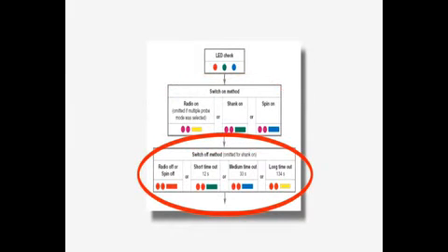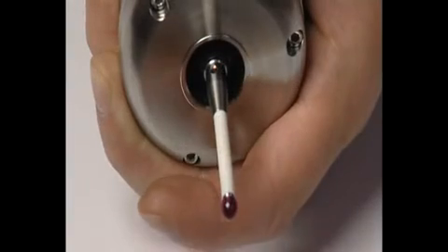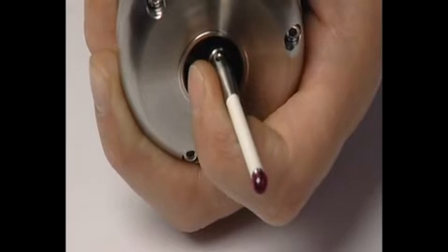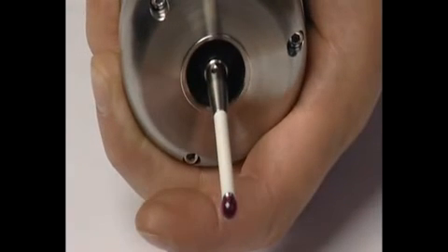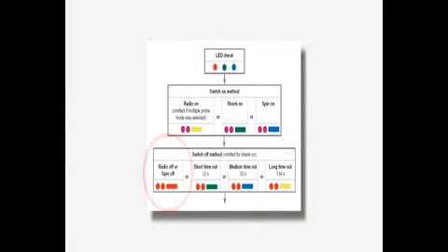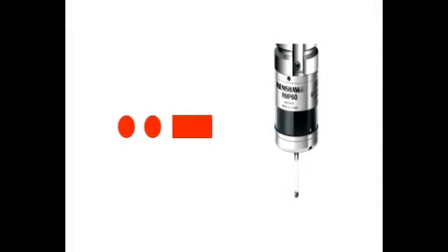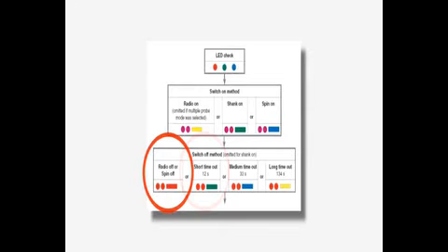The RMP60 has multiple switch-off methods. To change the switch-off methods, deflect the stylus for 1 second. The switch-off methods are red, red, red, radio or spin off, in which the RMP60 will accept a radio M-code signal or a spin off command at the speed recommended in the user guide for between 1 and 6 seconds.